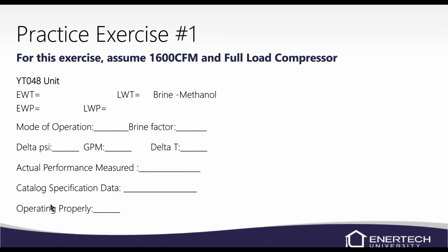So we're going to go through a few practice exercises real quick before we wrap up. In this example, we're going to assume that we're at 1600 CFM on a YT048 and we're in second stage. We're telling you that the brine in it is methanol, so we know that it's a closed loop system.